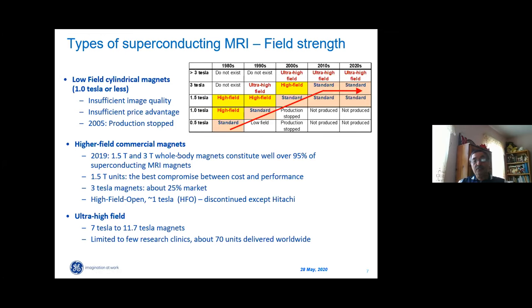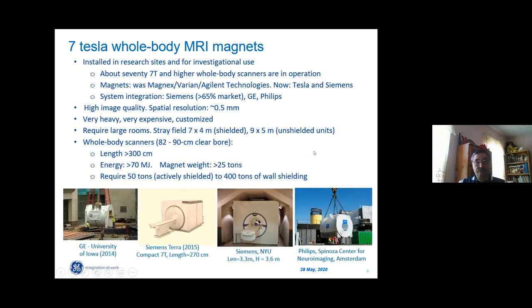So this is the picture of how field strength changed. For the first 20 years of the MRI industry, we were going up and up in field, but now the situation has practically stabilized. We have standard 1.5 Tesla and 3 Tesla scanners. We do not see commercialization of higher field scanners. 7 Tesla is one of the greatest achievements in the superconductivity industry. Just think a little bit. Niobium titanium, reliable, 7 Tesla, and the field on the conductor there is close to 8 Tesla, if not higher.